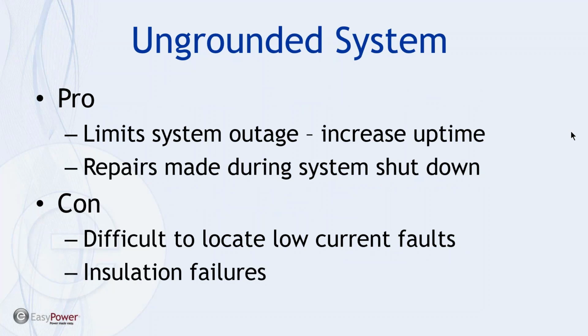And then the other alternative was an ungrounded system. And here are the limits of having one: a ground fault would not be detected, and consequently it increased the uptime of our system. And the idea was to make repairs during system shutdown so we didn't have to worry about the system being pulled down as frequently as initial minor fault repair would require.